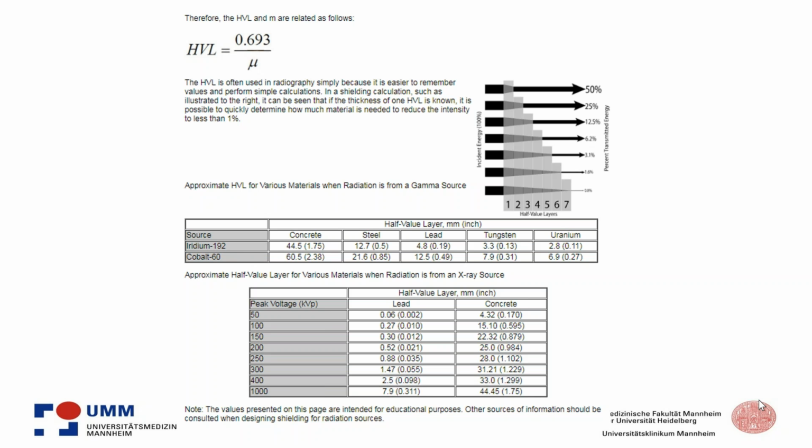You see the thickness of lead you need for a half value layer is much lower, depending on the energy, and you also see the corresponding concrete half value layer.